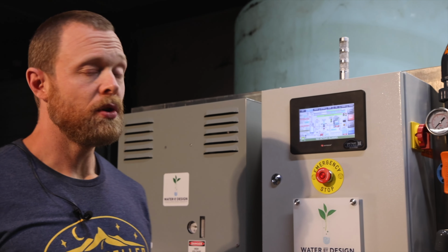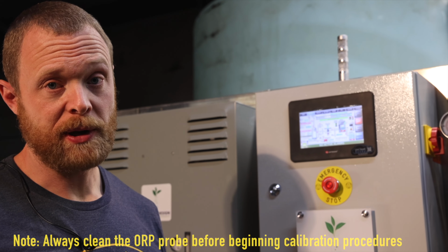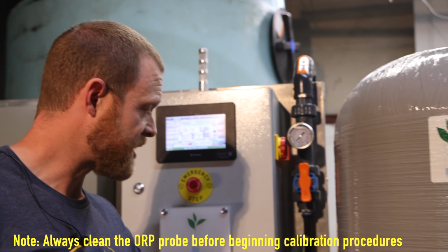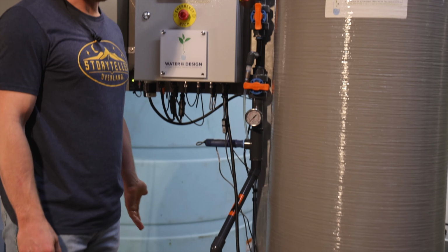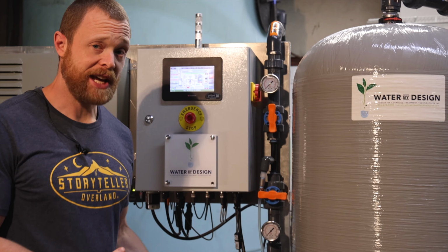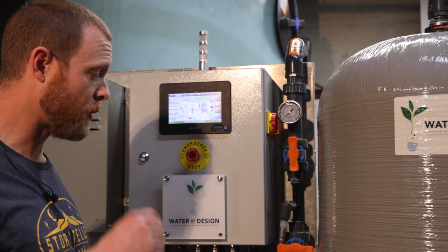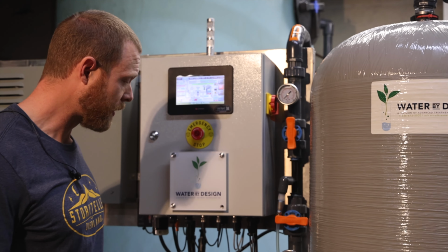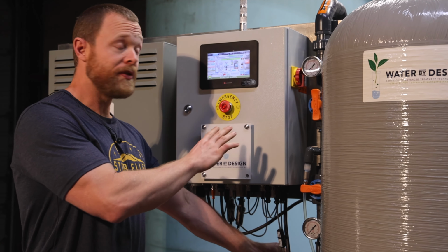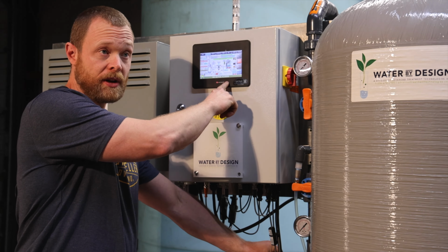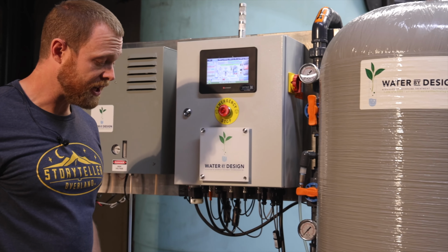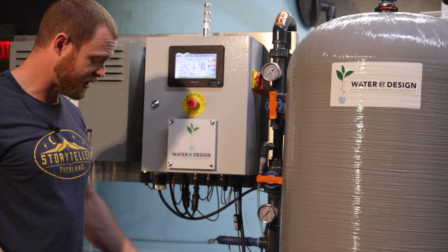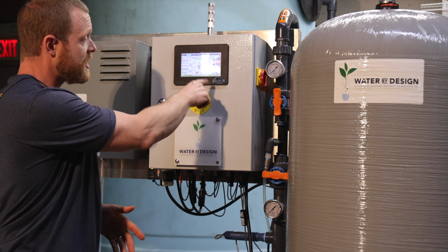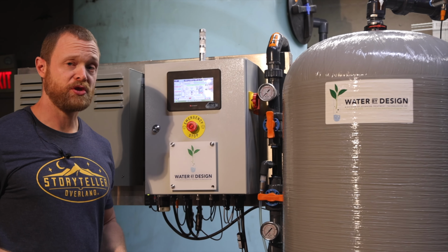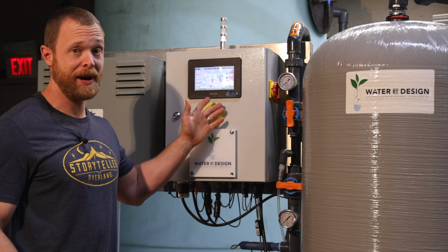All right, so when you're ready to calibrate your ORP probe, the first thing you're going to do is just isolate the probe by turning your valves, and that's just so we don't lose a whole bunch of water out of this. I'm not going to actually take this one out, just so we don't dump a bunch of water out, but you can see how that works. You'll then make sure that your system is powered on, but not running. So the reason is, obviously, we can't have the system running because we have everything deadheaded, but we're going to need to be able to read what's going on the screen. So again, not running, but powered on.